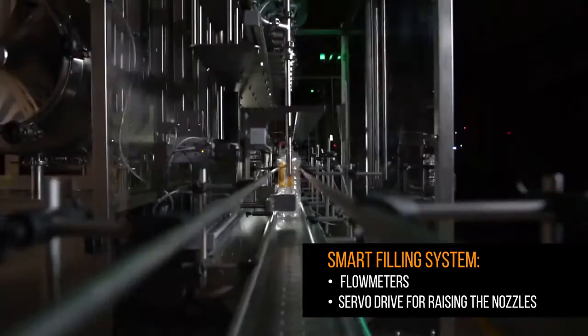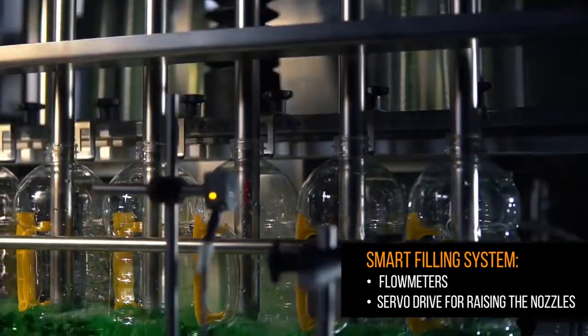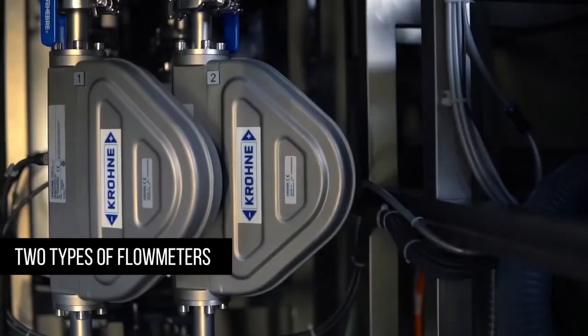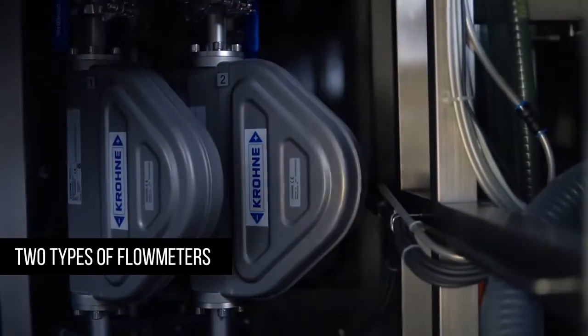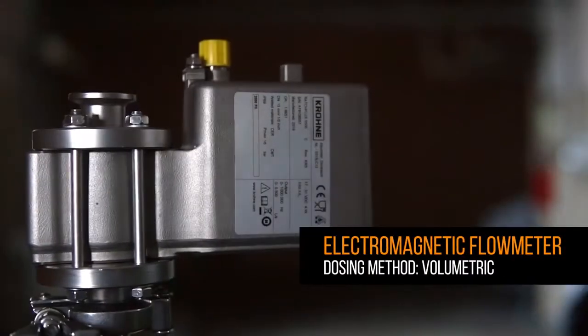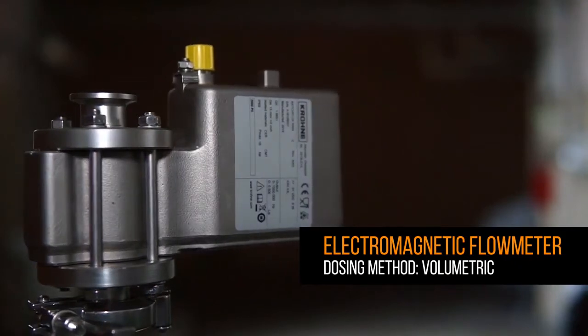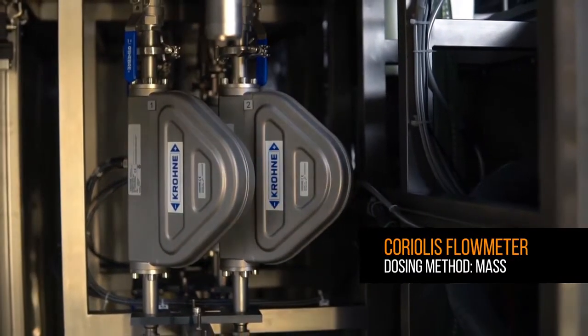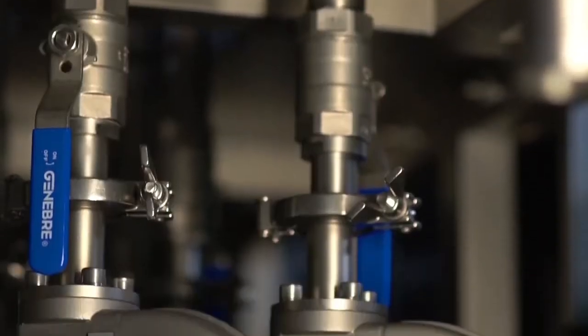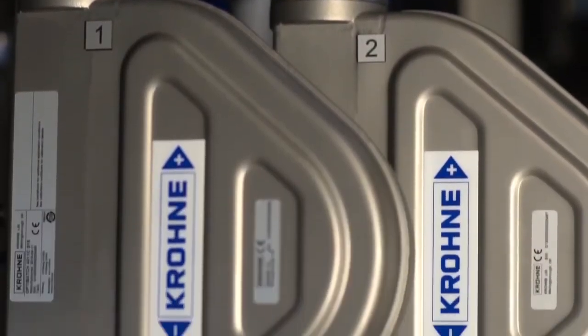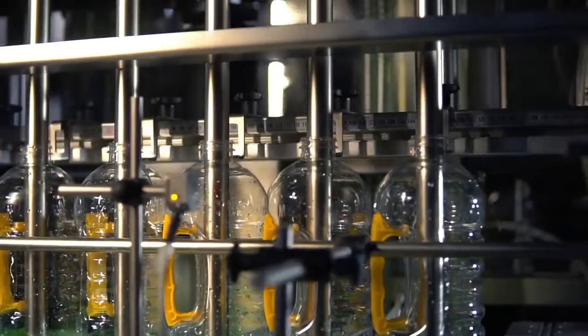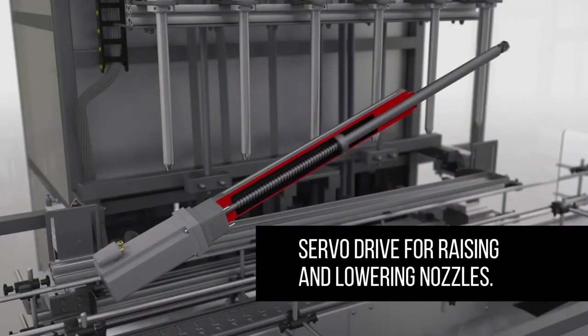The first element of the smart filling system is flow meters. They are of two types: electromagnetic flow meters are used for conductive fluids, while Coriolis flow meters are used for liquids prone to changes in physical properties such as density, viscosity, and volume. The choice of flow meter type depends on the properties of the product.